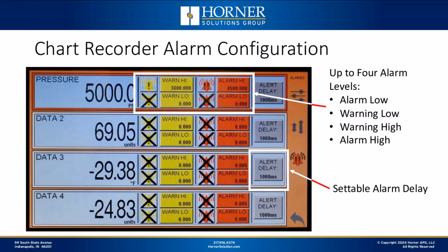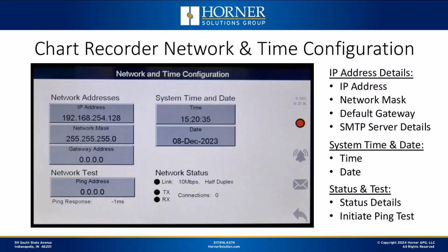So if you want to alarm, let's say, at 50 pounds per square inch, but you don't want to delay until maybe 5 seconds after you hit 50 pounds per square inch, then you could set up an alarm delay of, say, 5,000 milliseconds or something. So that's a settable parameter as well. Now, this unit has the ability to do some networking functions as well. We'll talk about that here in a minute.